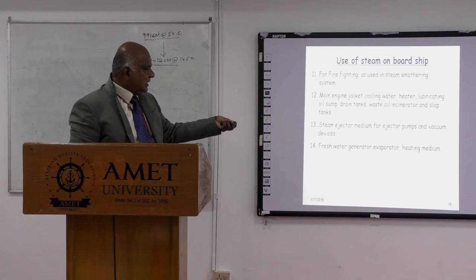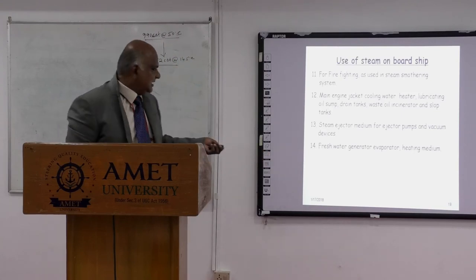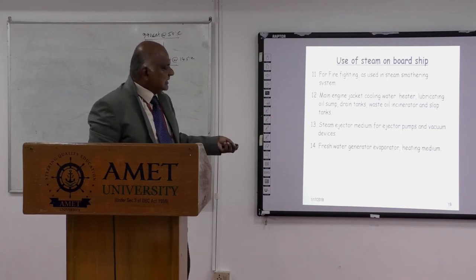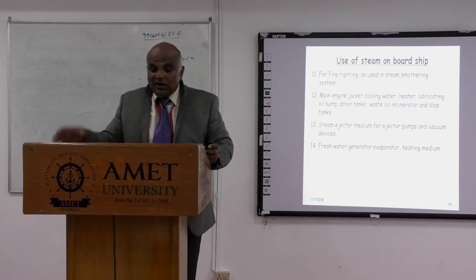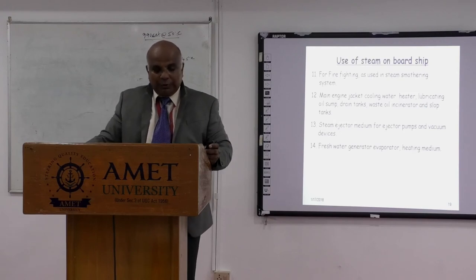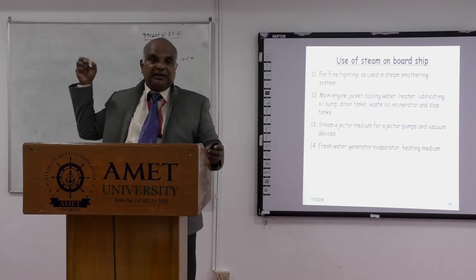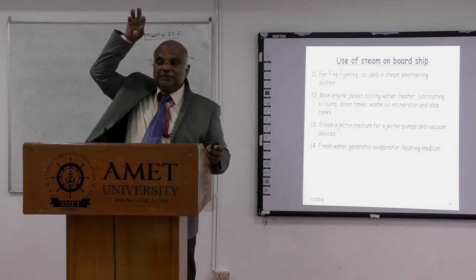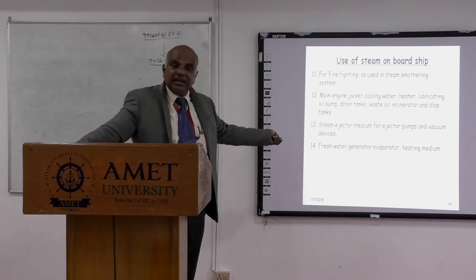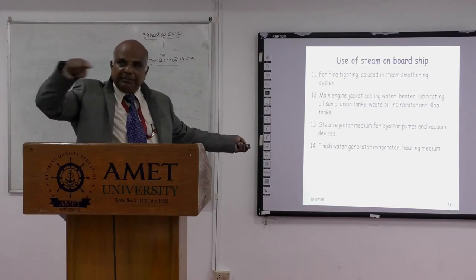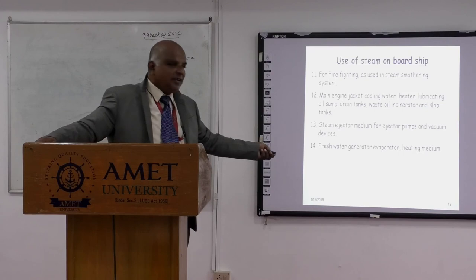Waste heat uses include incinerators, slop tanks, drain tanks, and lube oil heating for better circulation. Steam ejectors are used as a medium for vacuum devices — particularly on steamships where a vacuum is maintained on the turbine exhaust side using steam ejectors to improve turbine efficiency and RPM.